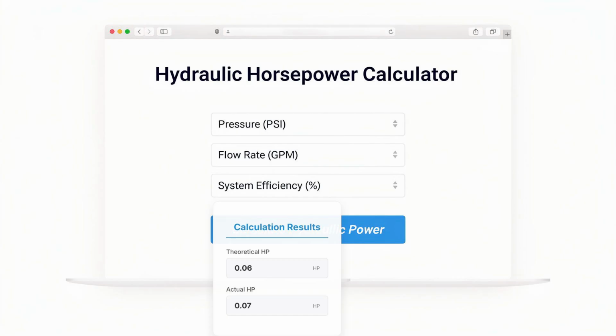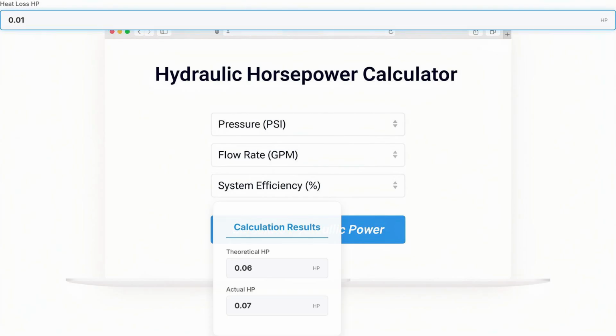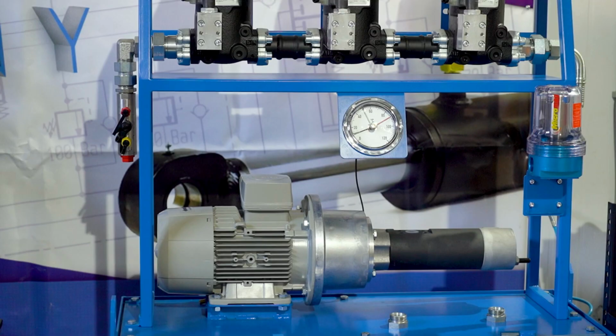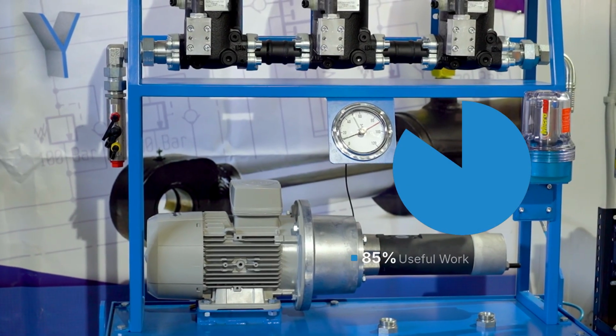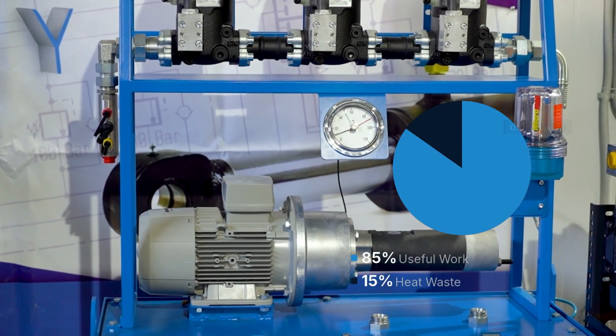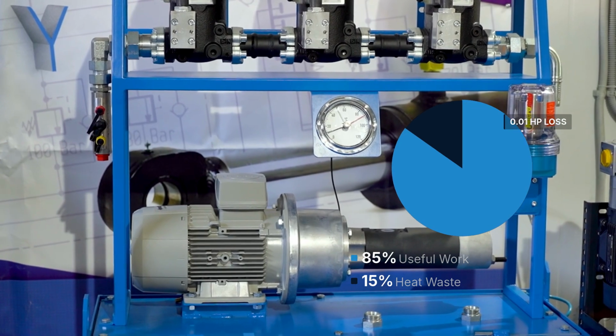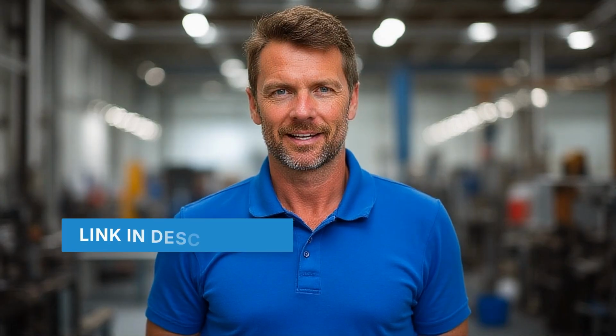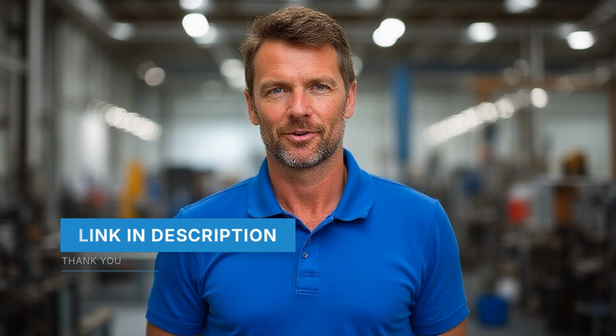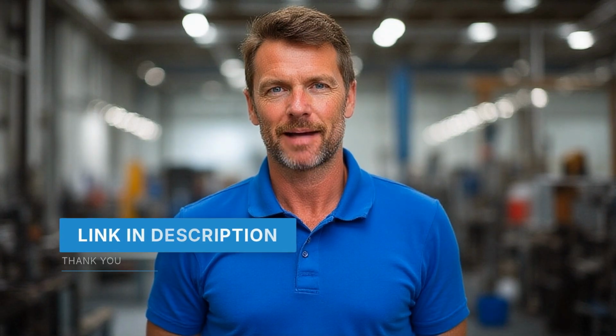The difference between these values appears as heat loss HP at 0.01, showing the power lost as heat due to the 85% efficiency. This means 15% of our input power, or 0.01 horsepower, is wasted as heat rather than useful hydraulic work. This calculator helps engineers properly size motors and cooling systems for hydraulic applications.